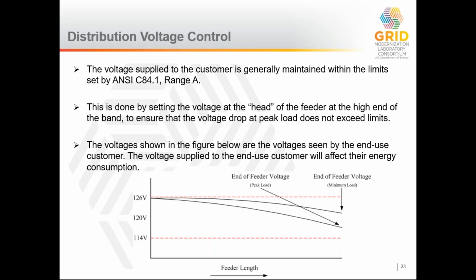But it will vary how much it drops over the course of the day. And in this figure, you can see two different traces where you have the end of feeder voltage at minimum load and peak load. At the peak load, the highest load of the day, you see the voltage is brought down a lot more than it is during the minimum load. This is also, it should be kept in mind, a conceptual drawing of an idealized single line going out.